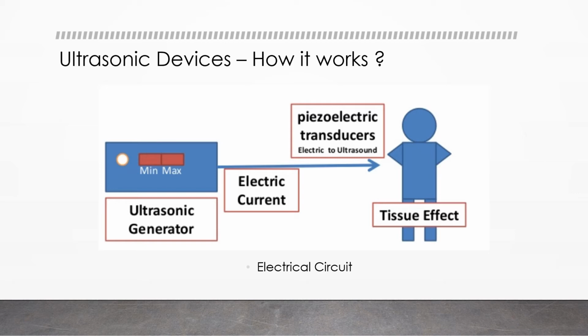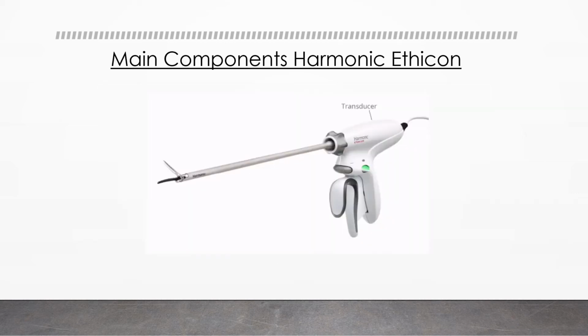So there is the ultrasonic generator. We send the electric current to the piezoelectric transducer that will change the electricity into ultrasound that will affect the tissue. For this slide, I will explain the functionality of the main components of the Harmonic Ethicon. As we can see in this video, the transducer converts electrical energy from the generator into mechanical motion using the piezoelectric effect.